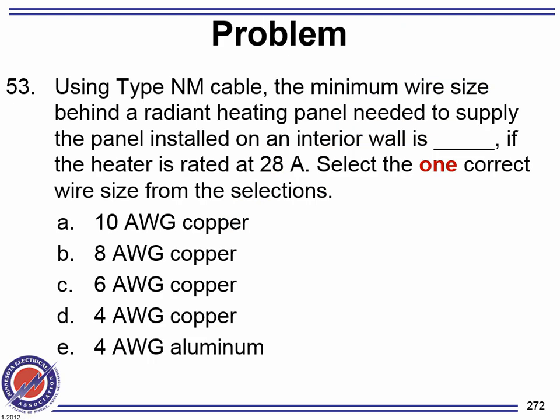Using type NM cable, what is the minimum wire size behind radiant heating panels? Radiant heating panels, guys, in Article 424, are considered as working at 40 degrees Celsius. If you put your cables behind the radiant heat, it's hot, so they consider it 40 degrees Celsius. What do you need to do then? Derate. All right, my amps are 28, gentlemen, so I need to find the ambient temperature and derate it.